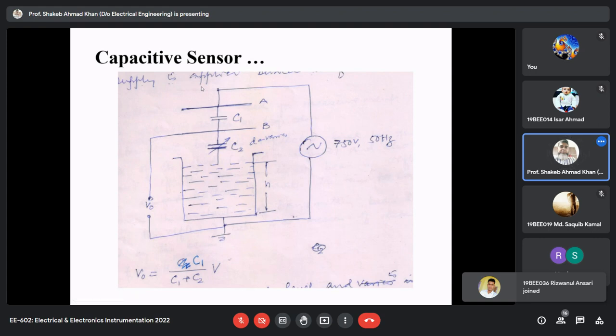So here there is formation of a capacitive voltage divider. One capacitance is formed between plate A and plate B, the electrode plates. Another capacitance is formed between plate B and the surface of the highly conducting fluid. So as the liquid level goes up and down, this capacitance C2 will vary.